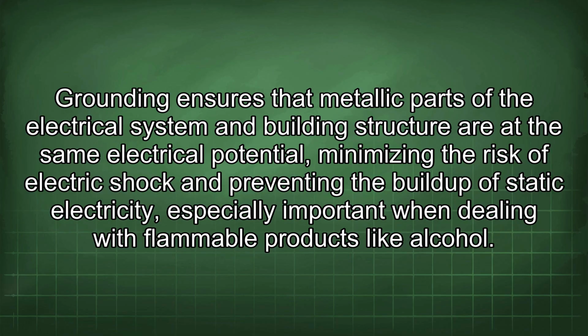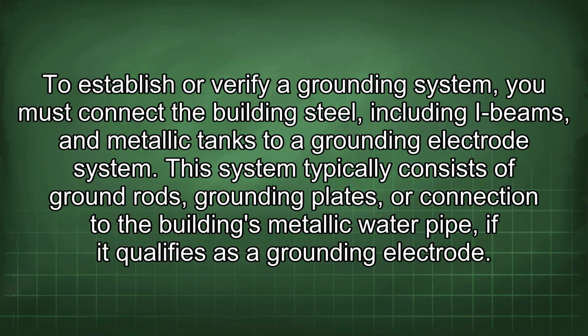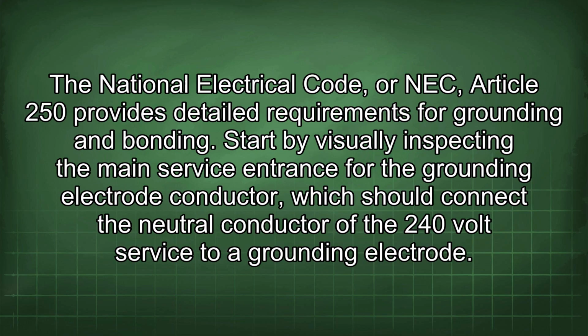Grounding ensures that metallic parts of the electrical system and building structure are at the same electrical potential, minimizing the risk of electric shock and preventing the buildup of static electricity, especially important when dealing with flammable products like alcohol. To establish or verify a grounding system, you must connect the building steel, including I-beams and metallic tanks, to a grounding electrode system. This system typically consists of ground rods, grounding plates, or connection to the building's metallic water pipe, if it qualifies as a grounding electrode. The National Electrical Code, or NEC, Article 250 provides detailed requirements for grounding and bonding.